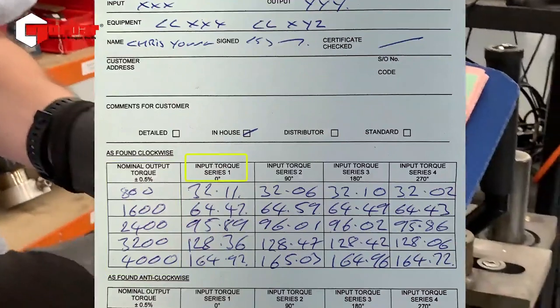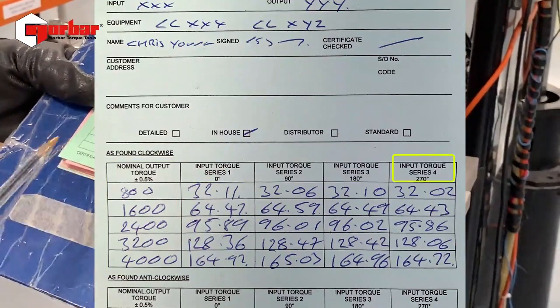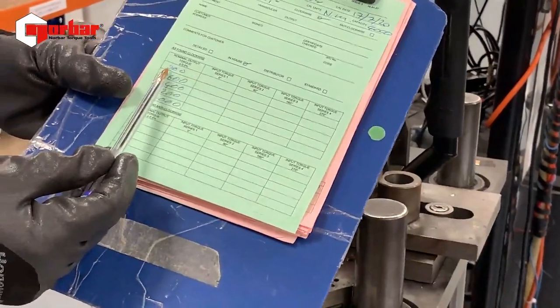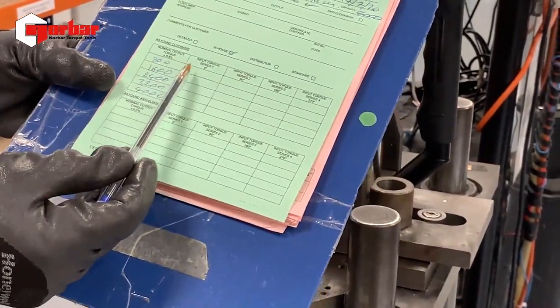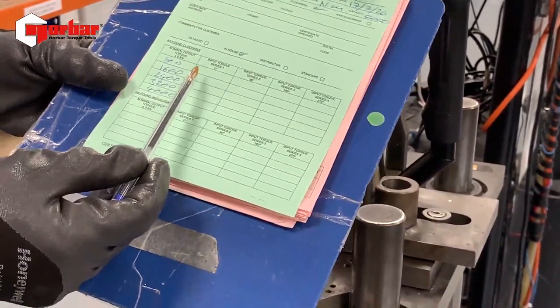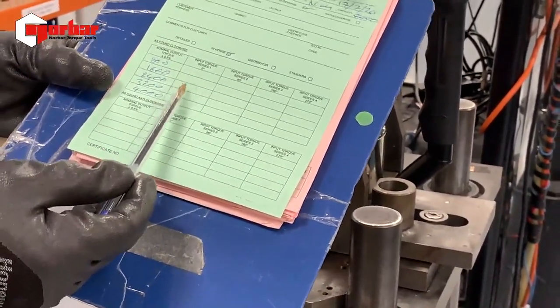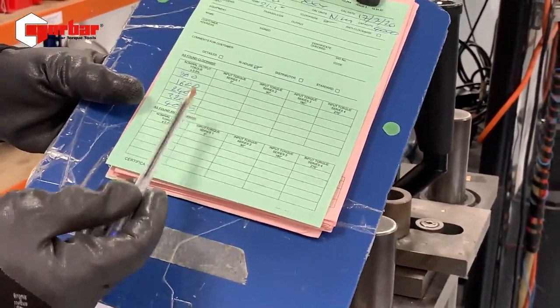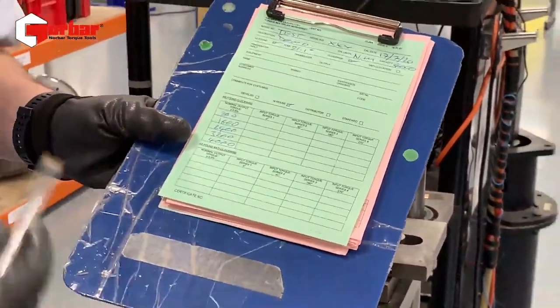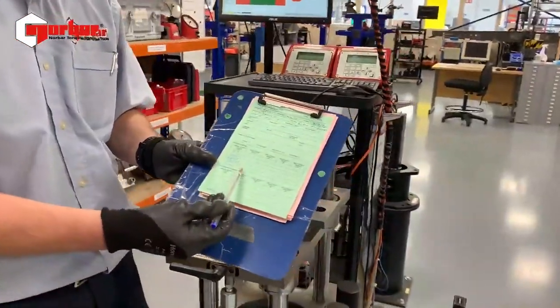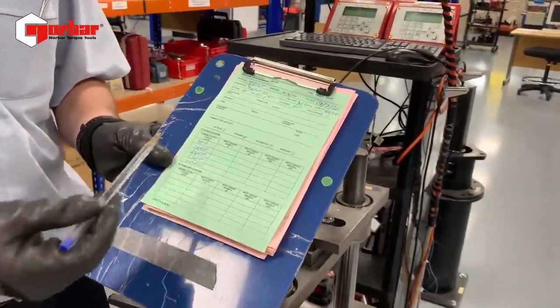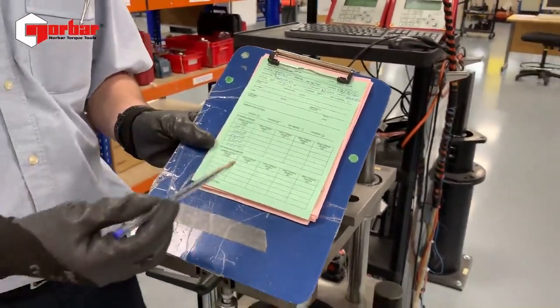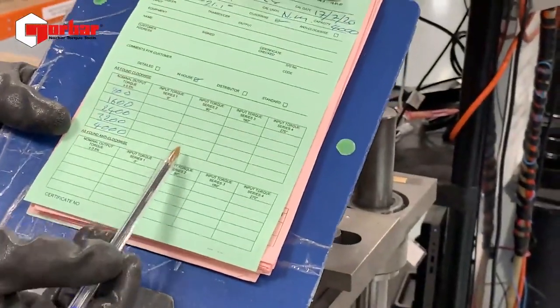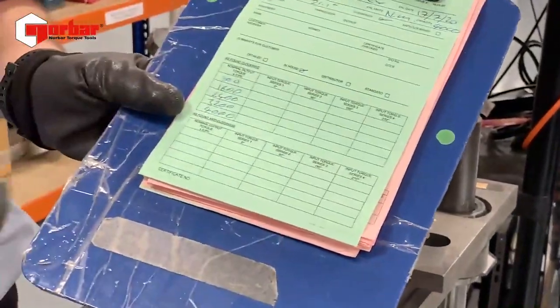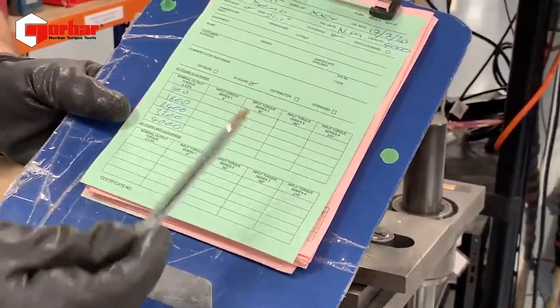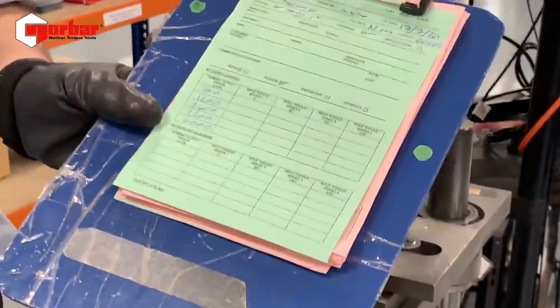Then we've got series 1, 2, 3, 4. For series 1, we're going to load to give us a nominal output of 800. We're going to record what that input torque value was. We're then going to go to 1600 and record that value, and so on until we get to 4000. Once we've done this, we're going to remove our load, and again we'll show you on the video how this happens. We're going to remove our load, turn the output of the HT through 90 degrees in the clockwise direction and repeat that test. We're going to remove our load, turn through 90 degrees, repeat, and do that one more time until we've got 4 planes of calibration.